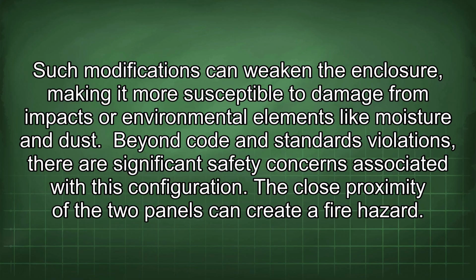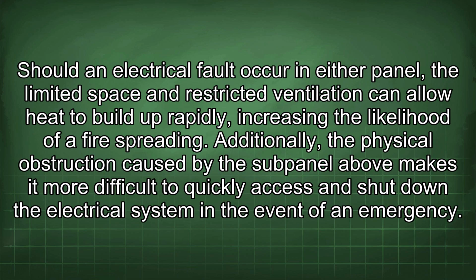Beyond code and standards violations, there are significant safety concerns associated with this configuration. The close proximity of the two panels can create a fire hazard. Should an electrical fault occur in either panel, the limited space and restricted ventilation can allow heat to build up rapidly, increasing the likelihood of a fire spreading. Additionally, the physical obstruction caused by the subpanel above makes it more difficult to quickly access and shut down the electrical system in the event of an emergency.